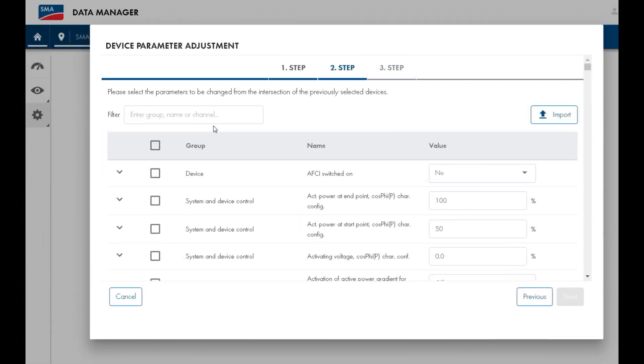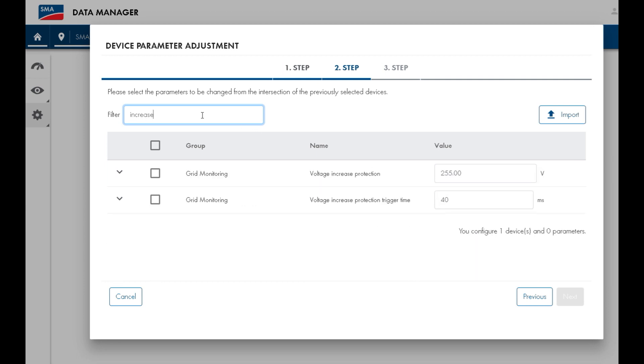We will now be changing the Voltage Increase Protection parameter, which is also known as VNOMMAX or Sustained Over Voltage Operation. The easiest way to find the setting out of this long list is to search the word Increase, and then you will find the setting called Voltage Increase Protection.